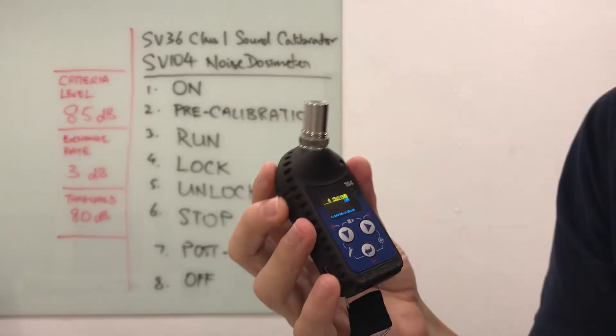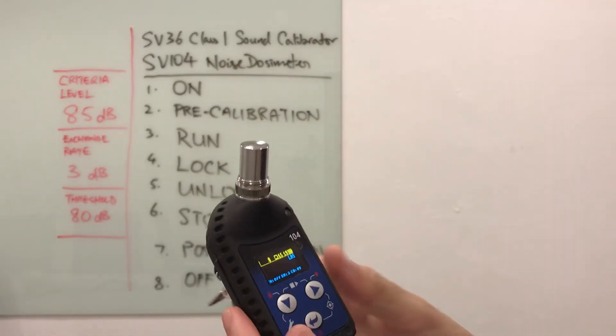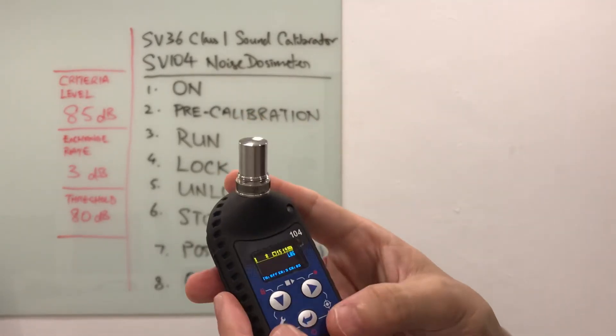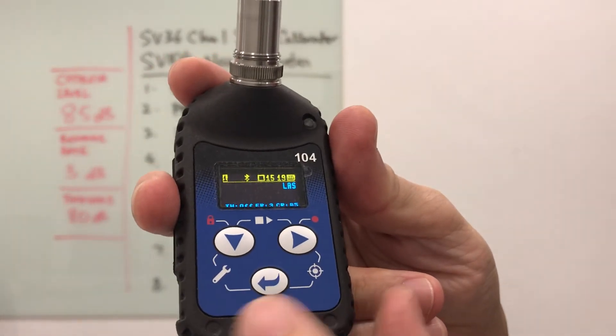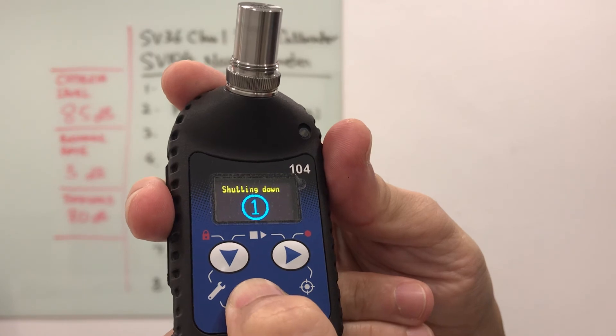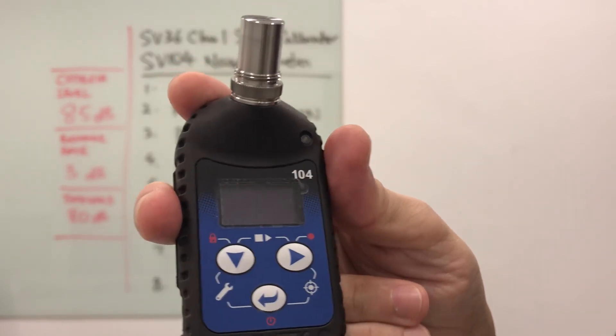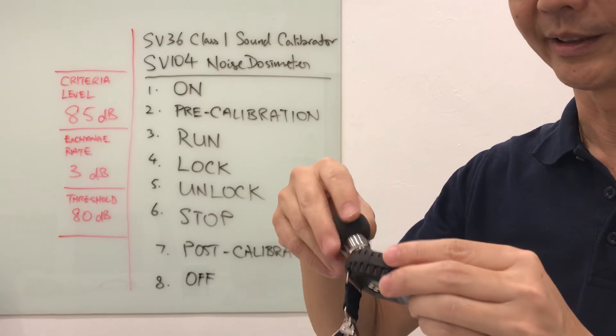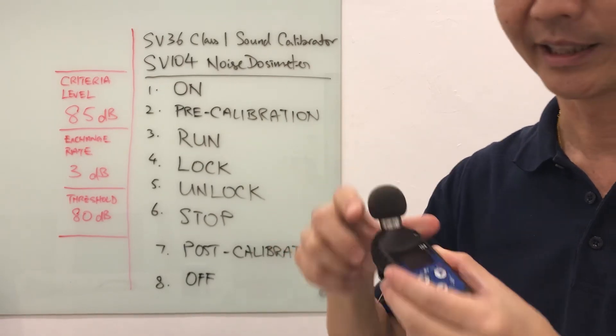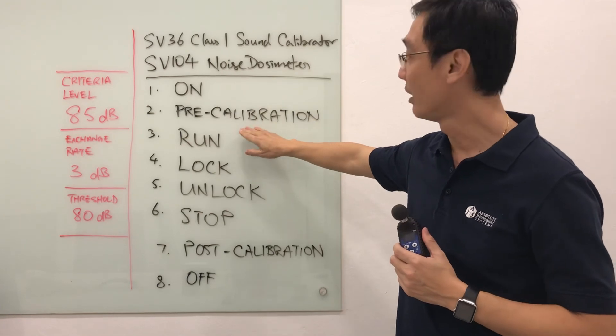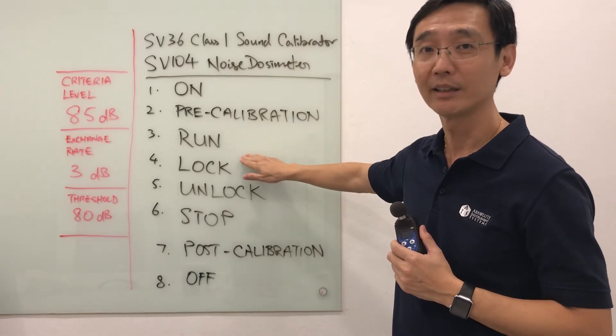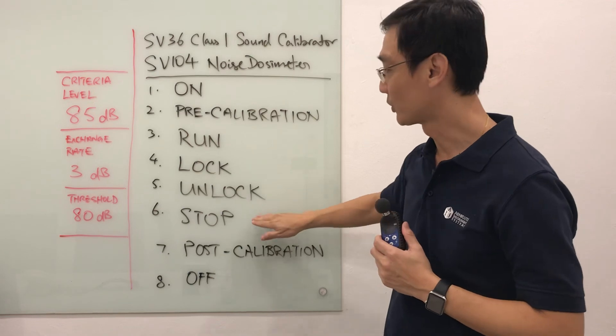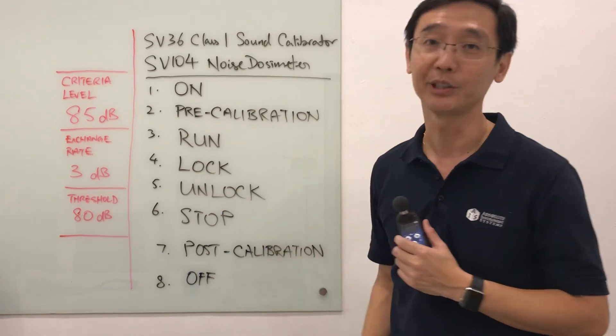Let's say I'm done. I'm ready to turn off the device and bring the equipment back. To turn off the device, the red button again, press and hold onto this on-off button and it will shut down. Remember to put back the windscreen. That's it. We have gone from on, pre-cal, run, lock, and then after that, unlock, stop the monitoring, do a post-cal, and we turn it off.